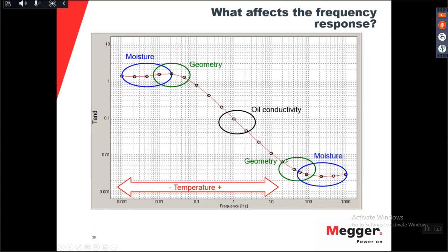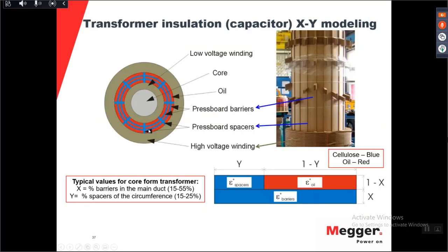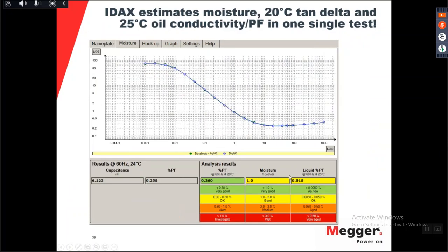The geometry here and here is, of course, how much paper you have, but the model is so intelligent that you don't need to know the geometry. You can just let the model find it yourself, and you will find the best fit, and from that actual response you will get the full moisture content. From one single measurement you will get the moisture content, you will get the 20-degree tan delta, the 25-degree oil conductivity in just one test.